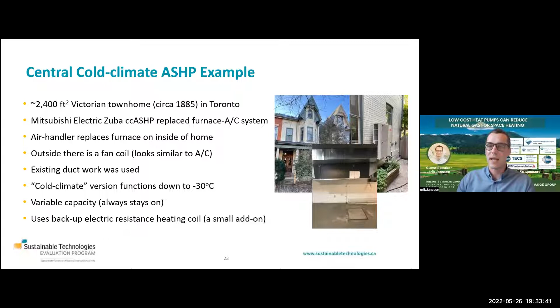This is beneficial for a few reasons: it's more efficient, more comfortable, and causes a little less wear and tear on the equipment because it's not banging on and off at full capacity. This retrofit also uses a backup electric resistance heating coil, which is pretty common with these retrofits. It's just a small add-on to the system, essentially a bit of redundancy for that rare, extremely cold day, to make sure there's enough heating capacity to maintain the thermostat set points of the home.